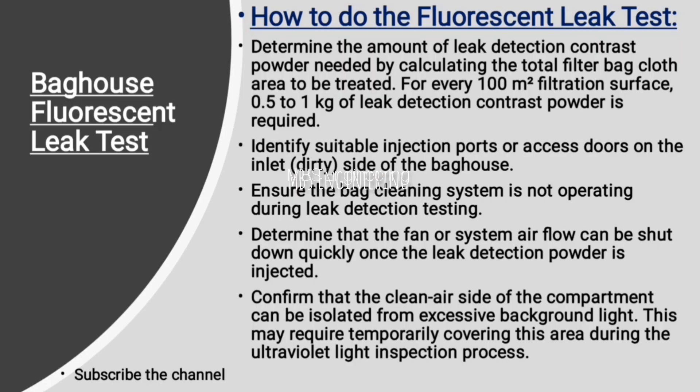How to do the fluorescent leak test. First step: determine the amount of leak detection contrast powder needed by calculating the total filter bag cloth area to be treated. For every 100 square meters of filtration surface, 0.5 to 1 kilogram of leak detection contrast powder is required. Next step: identify suitable injection ports or access doors on the inlet dirty side of the bag house. Next step: ensure the bag cleaning system is not operating during leak detection testing.